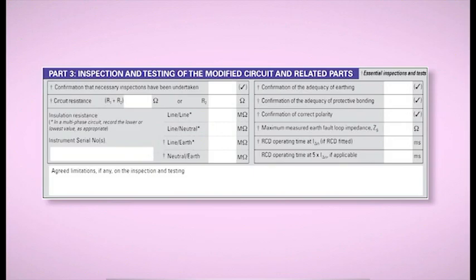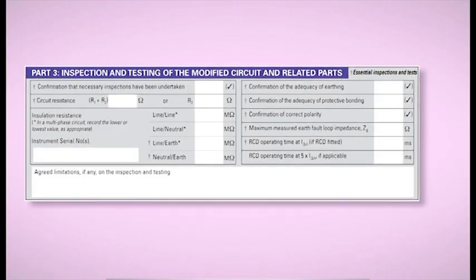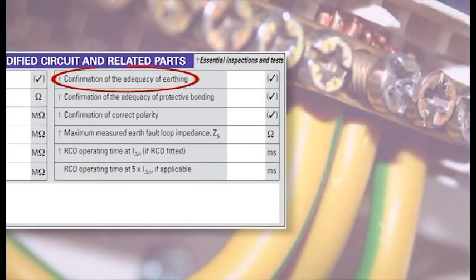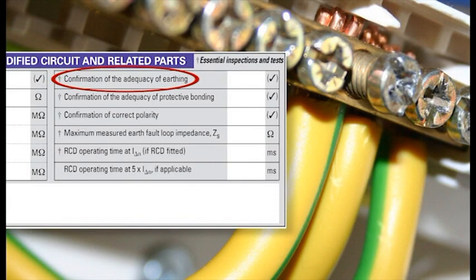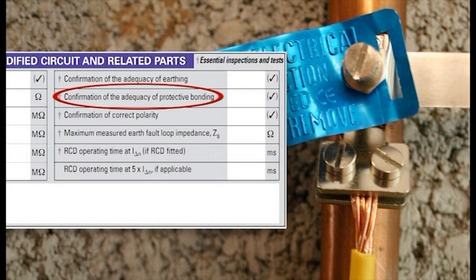I will point out though that although the minor work certificate is for an addition to a circuit, we are still required to verify by visual inspection that there's an earthing conductor connected to the consumer unit from the means of earthing, and also that where protective bonding is required for extraneous conductive parts, it exists.